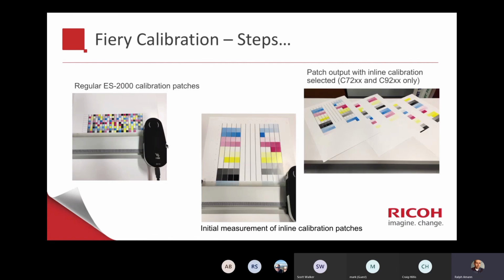Here's some shots of how that looks. Very important: some customers, even if they have a spectral, may have only used it by hand. If you select the newer patch sets on the left, with a lot of very small patches, you cannot do this by hand, so you need the guide from your kit. That's just a reminder. On the right side, you see what the machine outputs when you do the inline calibration, and it automatically spits out these 3 sheets at the very right.